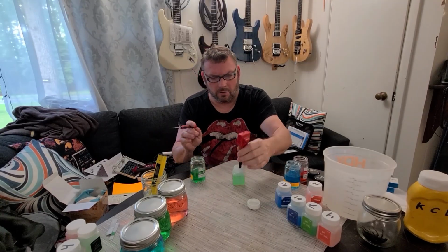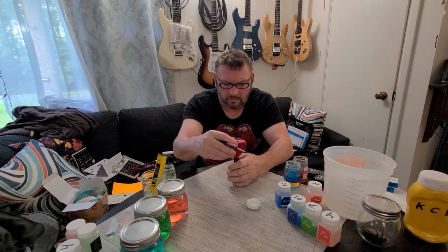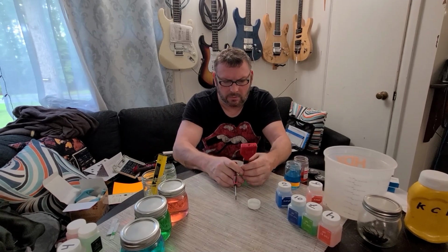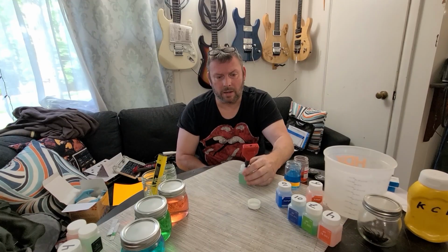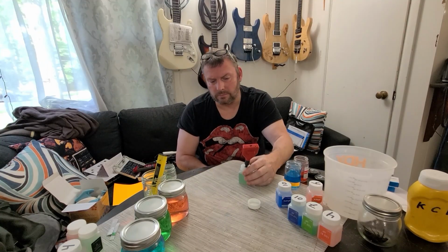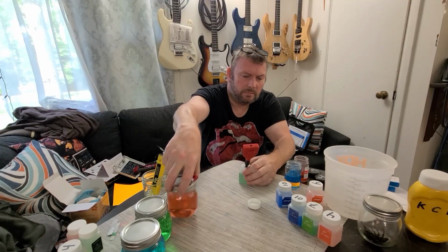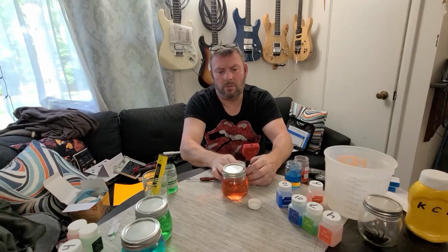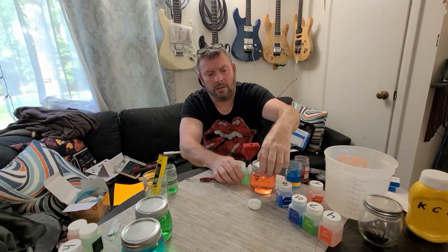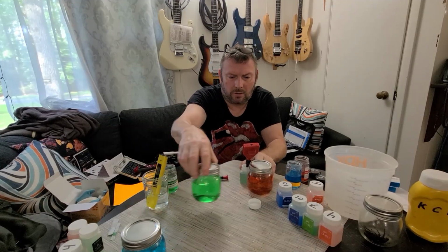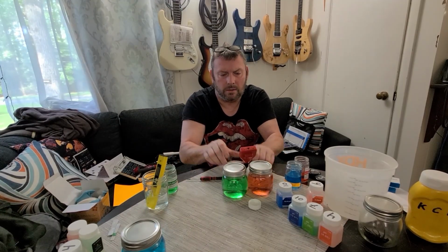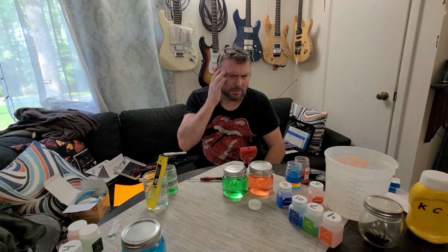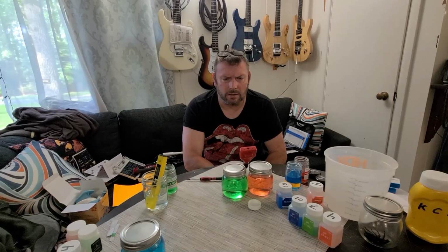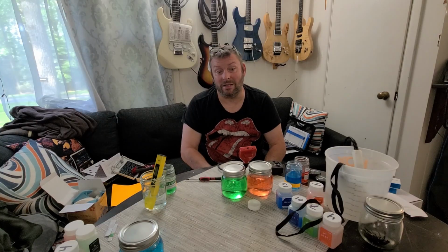So now I'm going to put it in what I know to be 7. I guess the secret here is don't move the cup. It does not like movement. Back down to 7, 6, 7, 5, 8. This thing would overwhelm. Yeah, see if it moves, it jumped up to 8. Good gosh, that's not right. So I guess what I have to do, boy, but how am I going to calibrate it if I can't move it? Oh, it just said 7.05, which is kind of where I want it to be. Boy, this thing takes a long time to focus in. About 7.6 is where this is at.